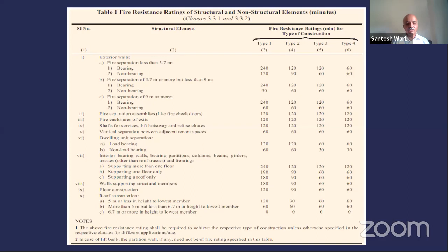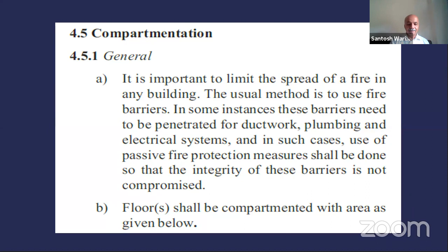We will go through the compartmentation as provided in the National Building Code, clause 4.5, wherein the building usually uses fire barriers. For instance, these fire barriers need to be penetrated for ductwork, plumbing, and electrical systems, and in such cases, passive fire protection measures shall be used so that the integrity of these barriers is not compromised. This is a very important part of the definition: you have fire-rated walls, but when services like ducting, plumbing, or electrical cables cross them, any penetration should be properly sealed so that the fire resistance of 120 minutes is achieved. In case of fire, it should not travel from one compartment to another through these openings. So that is the intent.